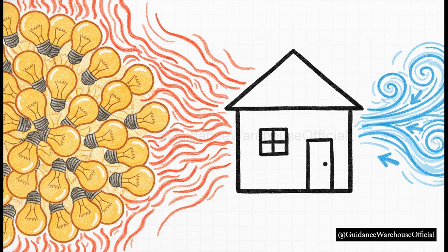Let's plug some real numbers into this. Say your house holds 836 kilograms of air, and a massive draft completely replaces all that air every 30 minutes. If we want to warm that newly incoming air by 10 degrees Celsius, plugging our numbers into those 3 steps tells us that replacing the convective heat loss requires 4.64 kilowatts of continuous power.